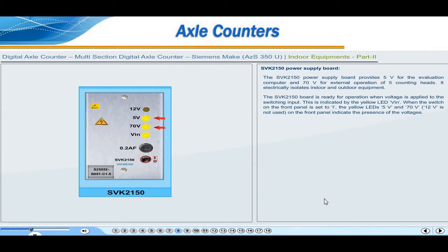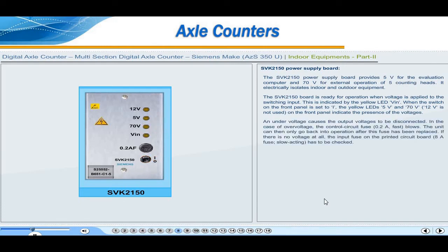When the switch on the front panel is set to I, the yellow LEDs 5 volt and 70 volt (12 volt is not used) on the front panel indicate the presence of the voltages. An undervoltage causes the output voltages to be disconnected. In the case of overvoltage, the control circuit fuse, that is 0.2 amperes, fast blows. The unit can then only go back into operation after this fuse has been replaced.